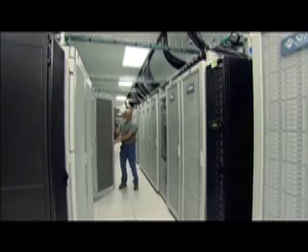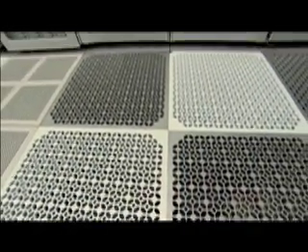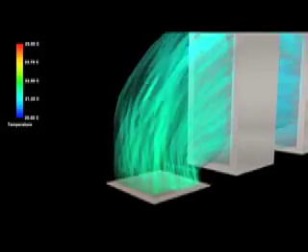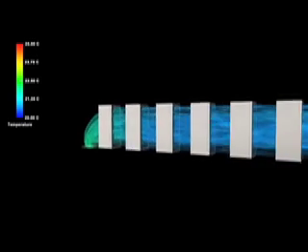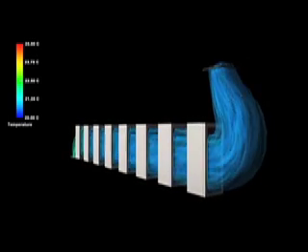In contrast, Red Sky uses a Glacier Door by Sun Microsystems — the first rack-mounted, refrigerant-based, passive cooling system on the market. The glacier doors cool the components, removing 90% of the heat load. This strategic cooling is further enhanced by feeding cool air through perforated tiles to the first row of cabinets. Cool air passes through the glacier doors from rack to rack by laminar flow. The air exiting the last rack is actually cooler at the end of the flow than at the beginning.